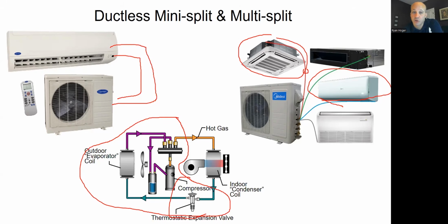However, this unit can only be in either heating or cooling at any given time. So if this guy wants heat, while this guy wants cooling, that's not happening. It's going to do one or the other. It can't do both, right? So if that scenario happened, this dude just got to wait. He can go ahead and turn off and just sit there and wait until this guy gets his heating needs taken care of. Then it can shut off and switch over and do this guy for cooling, right?